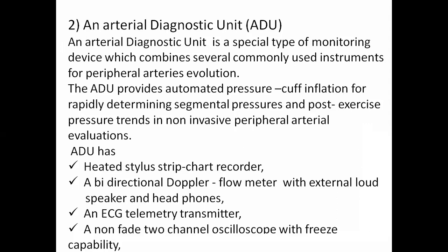Coming to the next one, an arterial diagnostic unit, ADU. An arterial diagnostic unit is a special type of monitoring device which combines several commonly used instruments for peripheral arteries evaluation. So for the determination of peripheral arteries evaluation, this arterial diagnostic unit is useful.